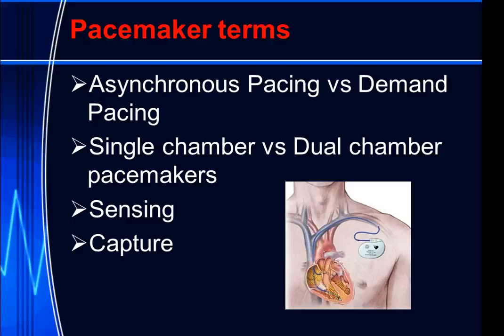A demand pacemaker can actually sense the heart rate. If it's set to pace at 65 beats per minute and it detects the heart is already beating at 65 or 68 beats per minute, it will not generate a pulse. These are very useful for patients who only occasionally have a low heart rate.